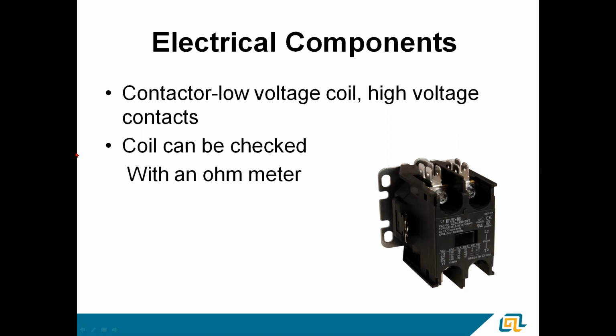The only caveat I'll throw out there is with Trane commercial equipment. Trane commercial equipment wants a 10 ohm contactor with no variance. If you get outside that 10 ohms, the board goes into a self-protection mode and it won't even energize that contactor. But the residential equipment, 20 to 25 ohms is usually what I'm seeing. Best thing I can say is if you ohm out that low voltage coil, you pull the wires off and ohm it out, and you've got less than 10 ohms there, you've got a shorted contactor on the residential side. So keep an eye out for that. You'll run into a couple of them this year, I'm sure.